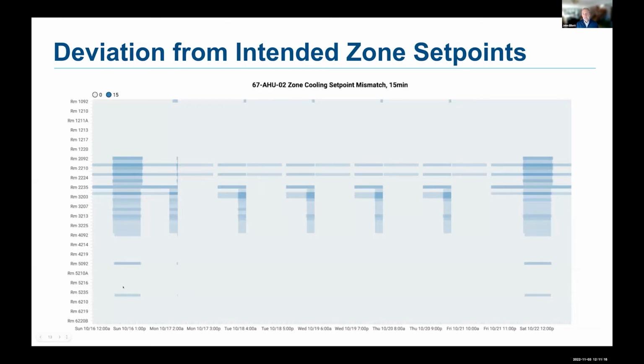And we can use, this is not the best graphic here, but we can use these heat maps that we generally use to identify periods. So this is a week-long period, and this is going across many different zones on the y-axis, and we can identify, for instance, in cooling, when we have set point mismatches happening from our intended set points. So if it's a small difference, it could be that someone has changed the temperature set point. If it's a large difference, in this case, it might be that we're operating outside of the schedule.